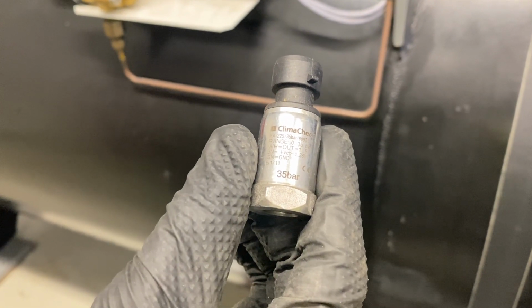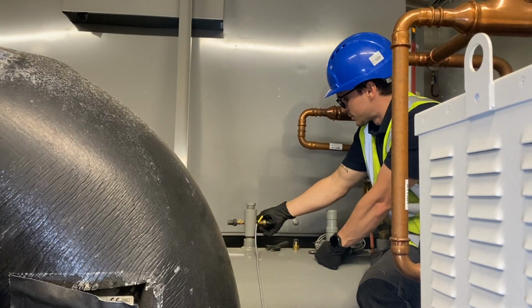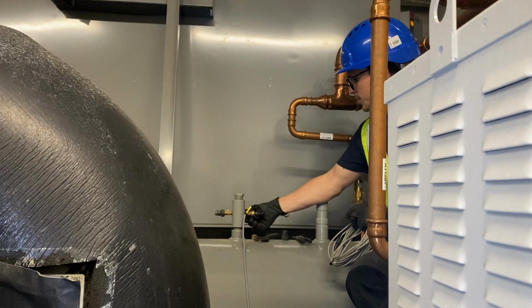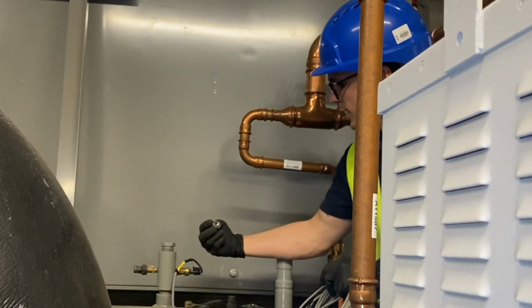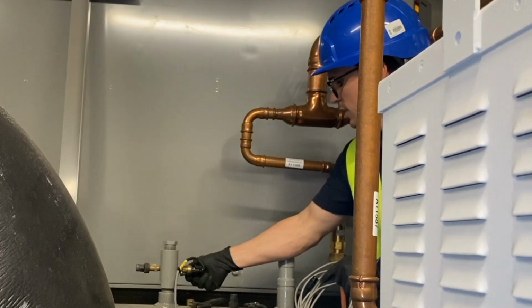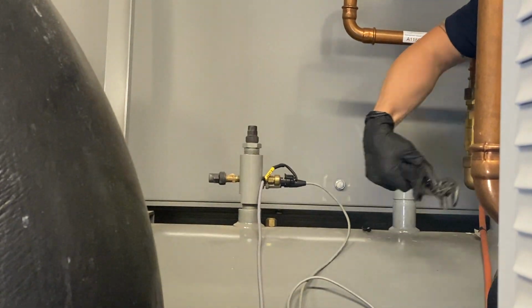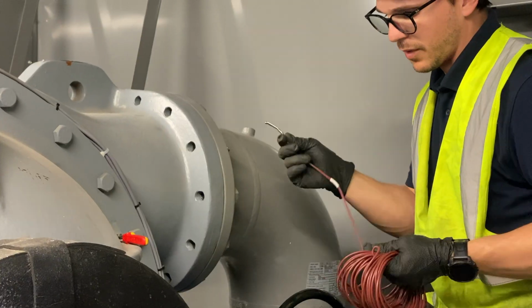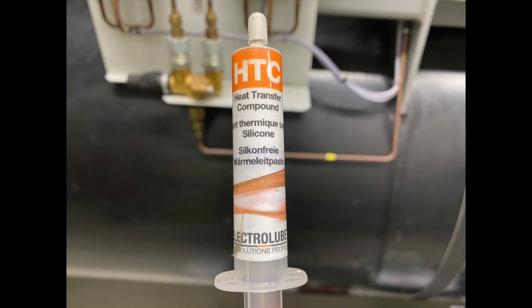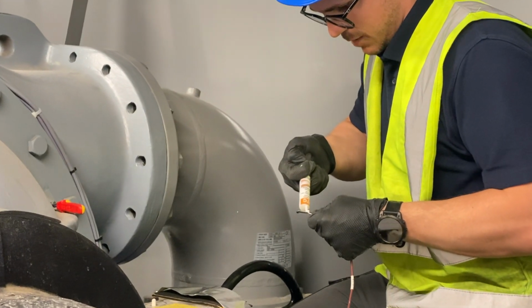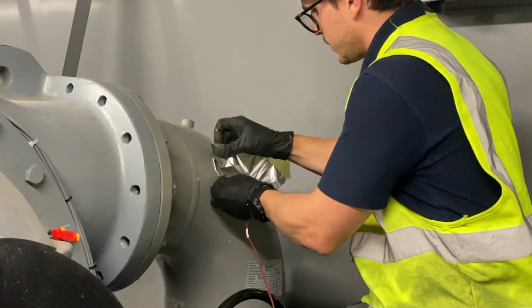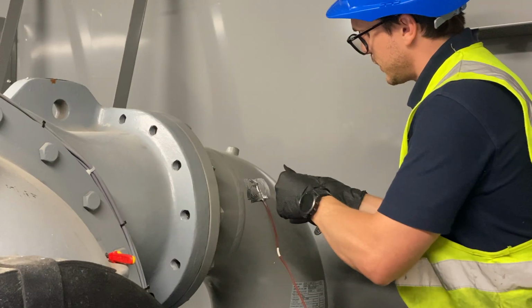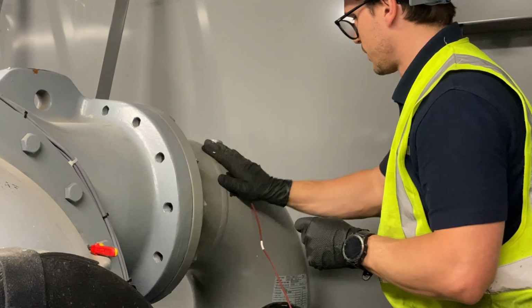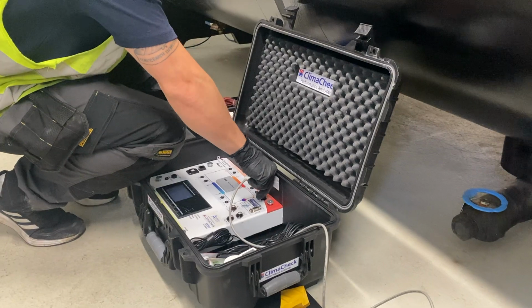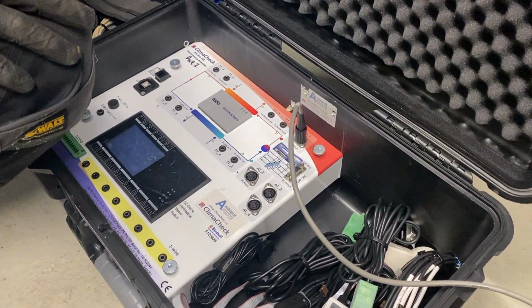Showing pressure transducers 35 and 10 bar. At the pressure access point we are fitting the high pressure transducer and sensor wire. Here the neoprene sealing ring is being pointed out. Next, preparing a temperature sensor and cable, demonstrating the heat transfer paste, applying paste to a sensor, then fixing it to the refrigeration discharge pipeline with adhesive tape and thermal insulation. Plugging in the discharge pressure sensor wire, then plugging in the discharge temperature sensor wire.